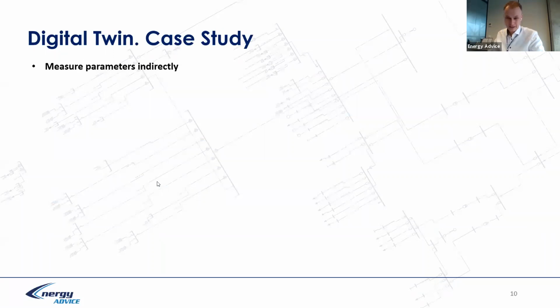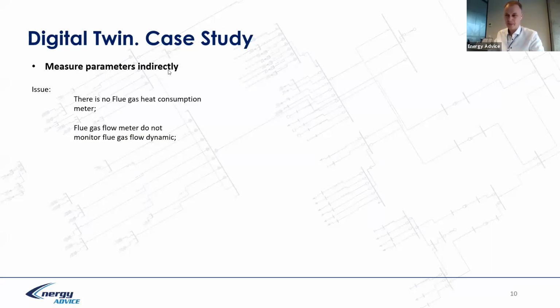So, a digital twin case study: measuring parameters indirectly. The issue is that there is no flue gas heat consumption meter. We have a client who does not have a heat consumption meter, because the heat is consumed from the flue gas with a heat exchanger, and the heat exchanger produces steam. So a flue gas flow meter was installed. We bought the flue gas flow meter. However, we found that this flow meter, due to its internal measurement technology, is not sensitive to the flue gas flow dynamics. So what to do?